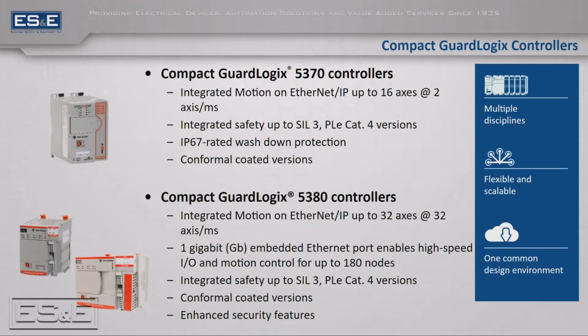So with Rockwell, there are two primary platforms. So there's the Compact GuardLogix, and then the traditional GuardLogix or ControlLogix GuardLogix. When we're talking about the Compact GuardLogix, there are two families of processors. There is the 5370, more commonly referred to as the 1769 platform, which was the original CompactLogix release. That version only comes in a SIL 3 or Performance Level E rated environment, and it does not have any of its own local safety I/O, which we will also cover later on in today's information.